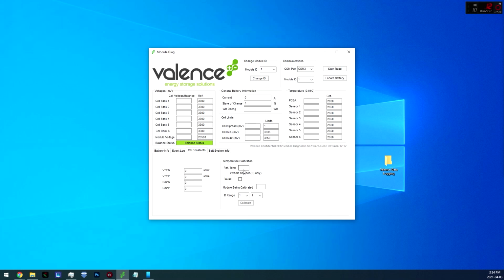You would set all the batteries in a room with a reference temperature, make sure all the batteries reached that reference temperature, and then type in what the reference temperature was in whole degrees Celsius only.